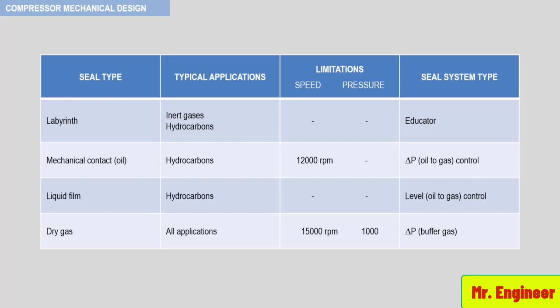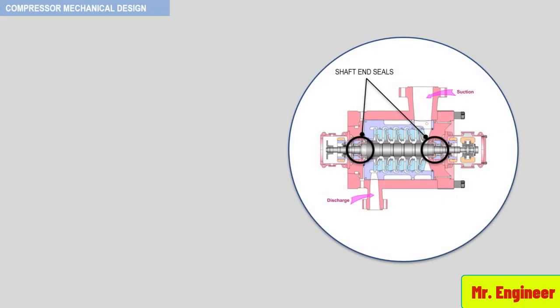With the exception of labyrinth seals used for inert gas services, all compressor seals are configured as double seals. The sealing fluid is supplied at a pressure greater than the process fluid and therefore requires a seal between the process and the sealing fluid, and between atmosphere and the sealing fluid. In the next couple of videos, we will examine in detail the major types of mechanical seals used for centrifugal compressors.